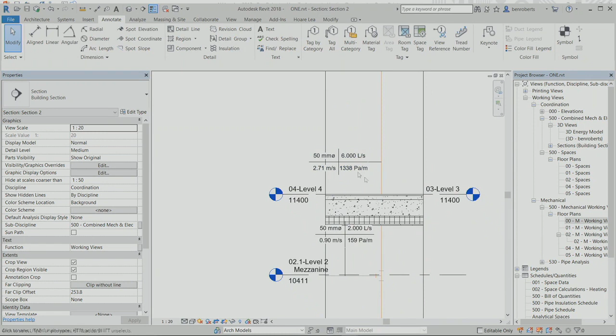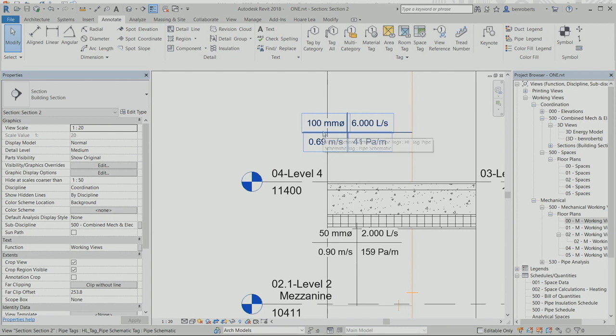So even at this stage, I can just select the whole pipe run and use the duct and pipe sizing tool. This is sizing things based on values I've put in already, just that I want a maximum friction of 220 pascals and a velocity of 1. You can change that to whatever you like, and it should be relatively quick. So that will just update. It's changed the size, now it's a 100 mil pipe and more sensible pressure drop values.